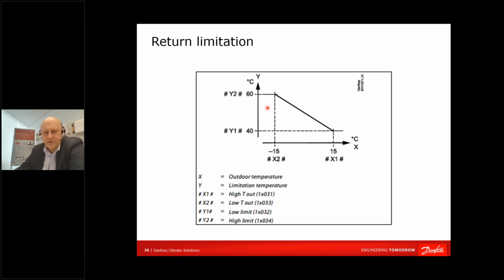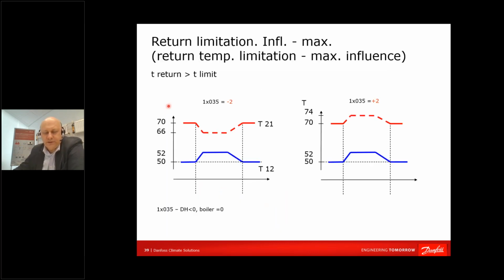Return temperature limitation, that is something which is needed by district heating utility, which would like that buildings are not wasting energy, because if you're returning high temperature, you are wasting energy at all, because you did not consume the product, you did not purchase product correctly, or you just wasted your food, you are just throwing it away. So return temperature sensor should be there, and you can set limitations in there too.